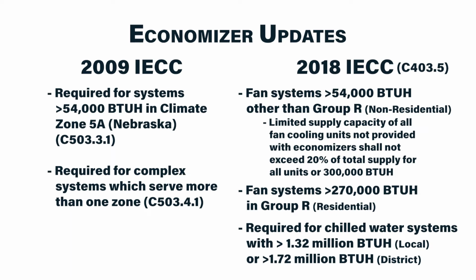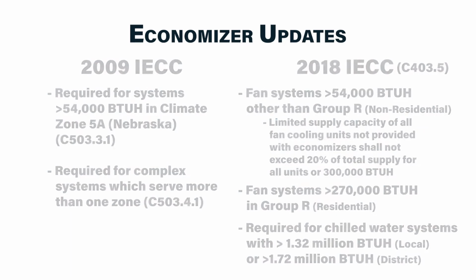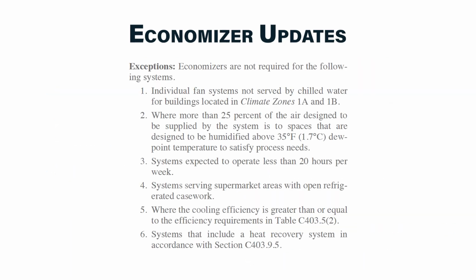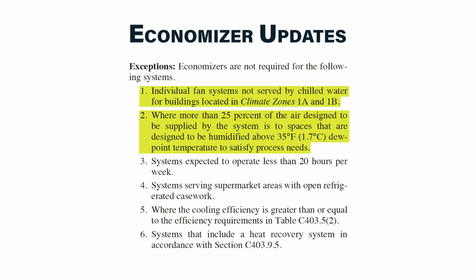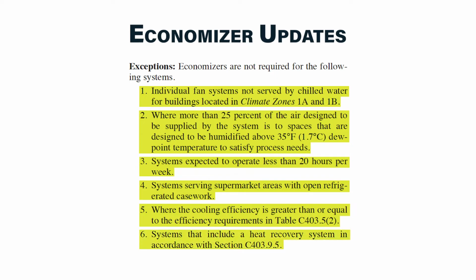This is basically saying that you can't put in a bunch of small 4-ton units, which wouldn't require economizers, to get around the requirement of having an airside economizer for larger systems. There's a number of exceptions to economizer requirements, particularly for special use cases, systems that don't operate often, supermarkets with open refrigerated cases, if you have really high efficient cooling equipment, or systems with heat recovery.